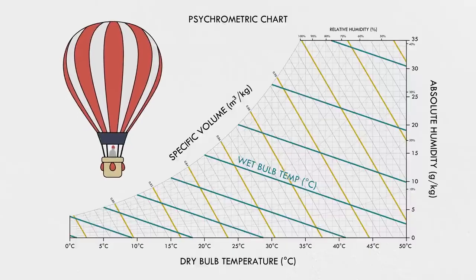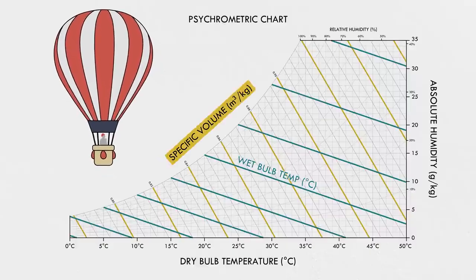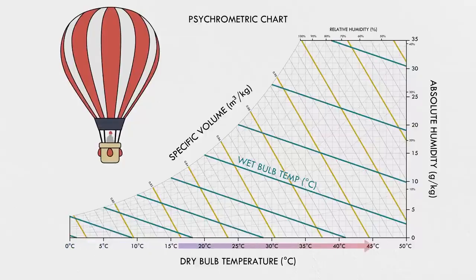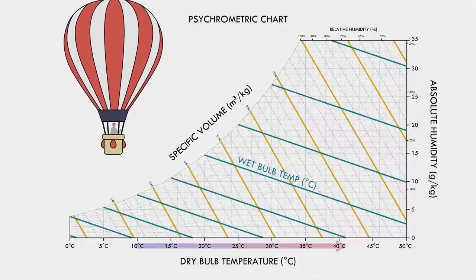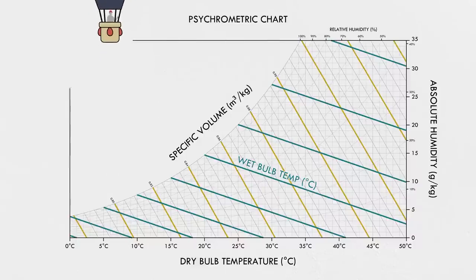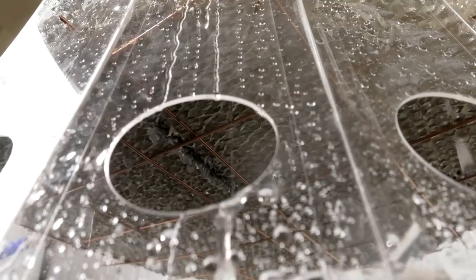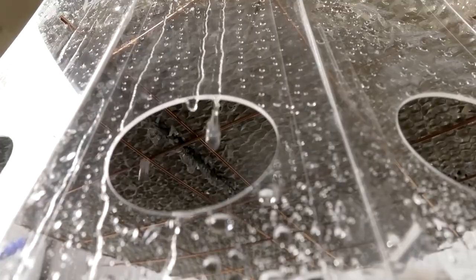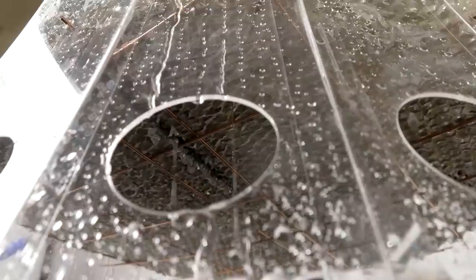Confusingly, the psychrometric chart actually shows specific volume, which is the inverse of air density. So as you move up in temperature, these lines slope downward. Hot air rises, most of us know that. But maybe less intuitively, it's also true for humidity. If you hold the temperature constant and just increase the amount of water in the air, its density goes down. Water molecules actually weigh less than the nitrogen or oxygen molecules in the air, so humid air is more buoyant than dry air. And this is the second key to a cooling tower: convection. The hot water transfers its heat to the air, the warm air becomes buoyant, flowing upward in the tower and drawing fresh air in through the intakes.